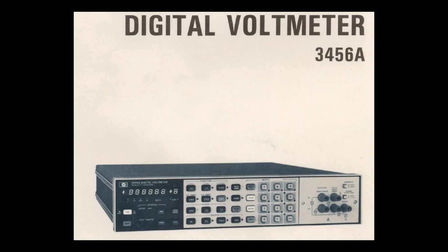Here we will be examining the HP3456A digital voltmeter. In this series we will be looking at a unit that fails with an overload error, and error code 4. These errors are a common problem with this unit. Along with fixing this error we will perform a few upgrades along the way. In this first part of the series we will perform the self-test, and see what the symptoms are.